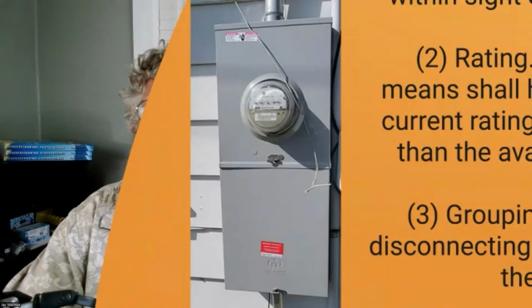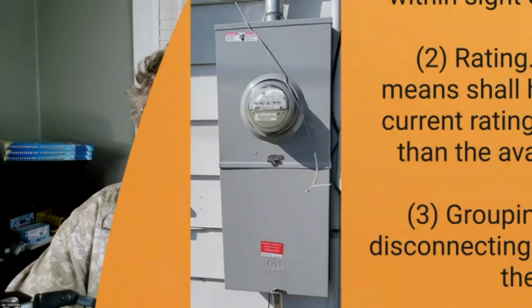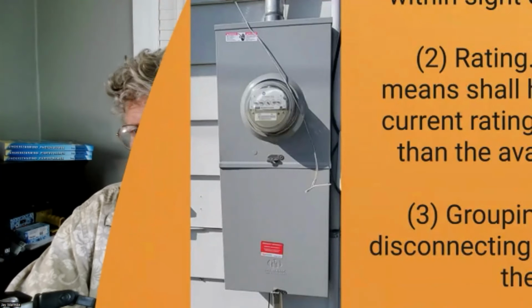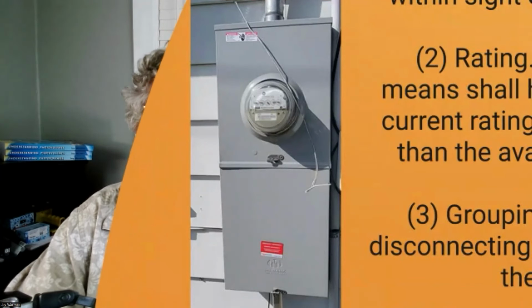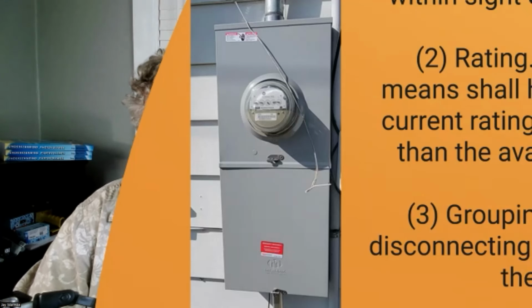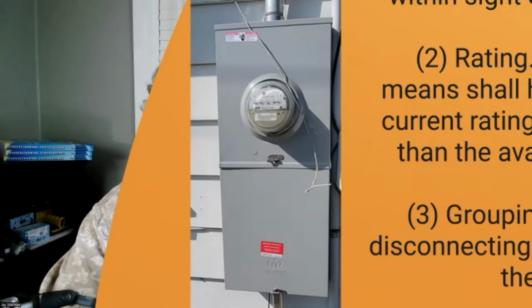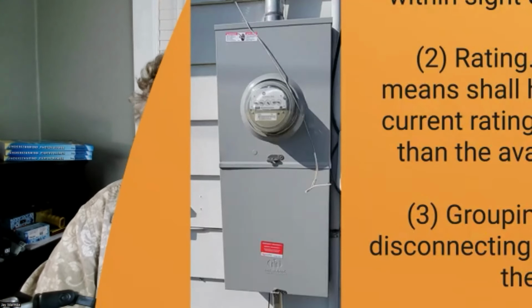But anymore, this is what you're going to need. Right below that meter box, you're going to have what looks like a very small service panel. Inside there's an emergency disconnect, just a double pole breaker. That's not going to be your main disconnect, that's going to be your main breaker. And then oftentimes there are 4 to who knows how many, 20, 30. You could have a whole sub panel underneath there, with another bunch more breakers available. And while I'm on that subject, I should point out for those of you who do electrical work, this might not occur to you, but in your main service panel, you're allowed to bond together the neutral and the grounds, the equipment grounds.